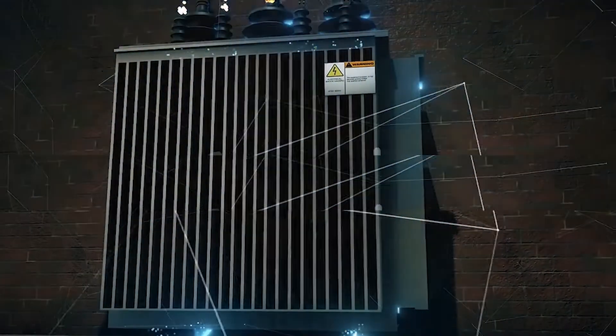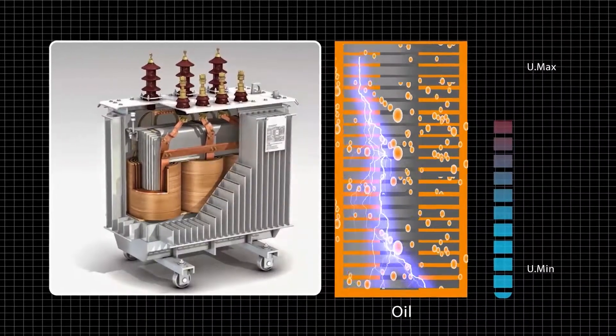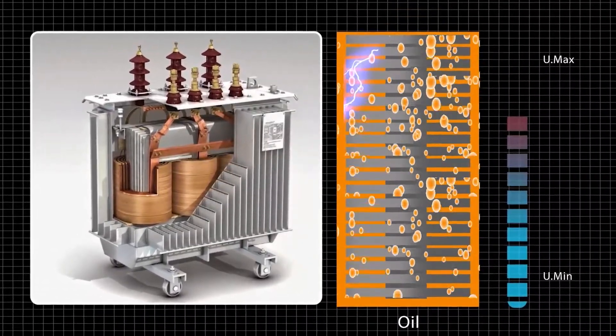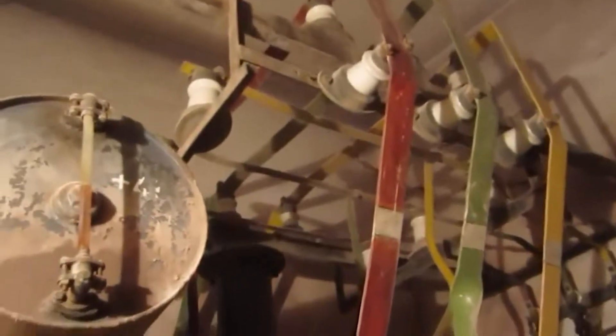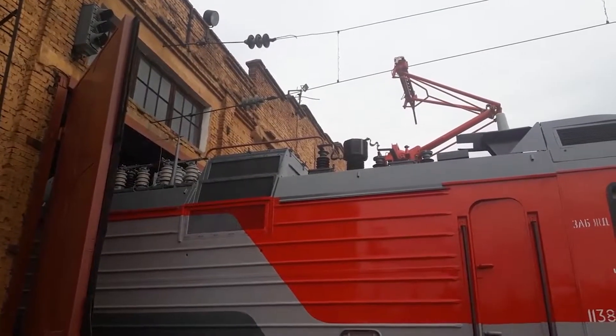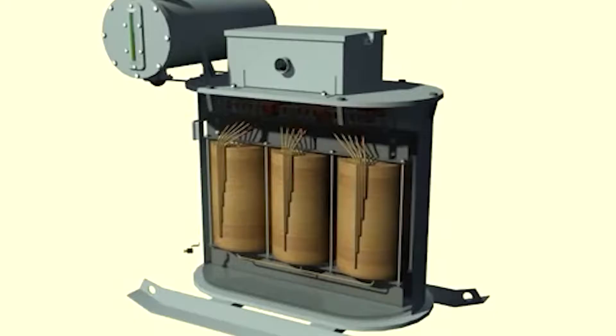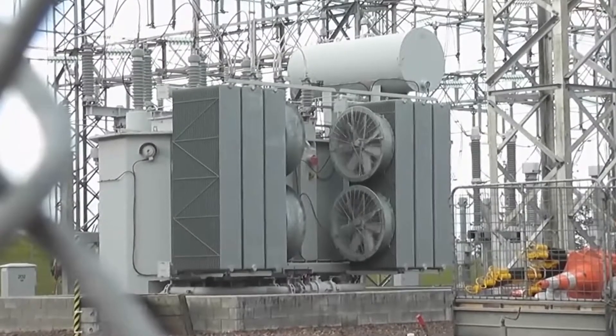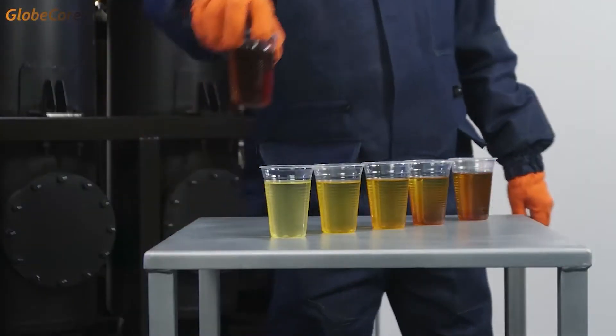If we draw an analogy with transformers, then insulating oil is a transformer's blood, which can be sampled to determine the condition of the system. This is especially relevant for transformers that have been in operation for more than 20 years, as well as special transformers operating under heavy loads — traction, mining, ship, electrical furnace, and others. In order for diagnostics to be effective, it must be continuous and include identification of all peaks and minimums of important parameters, to identify sharp deterioration in the condition of the oil.